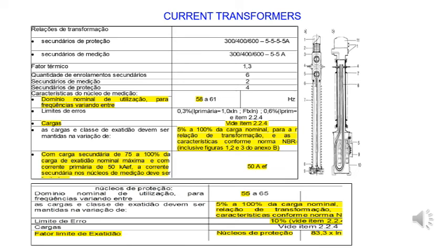This would damage the secondary windings. And there is a test to check that when a short circuit passes in the primary side, the current in the secondary side is limited to something like 50 amps, which will not damage the wires and so on.